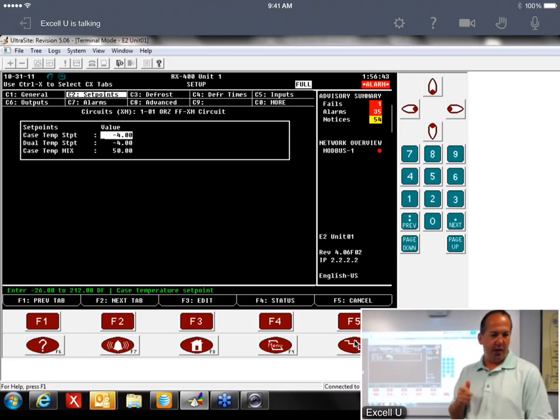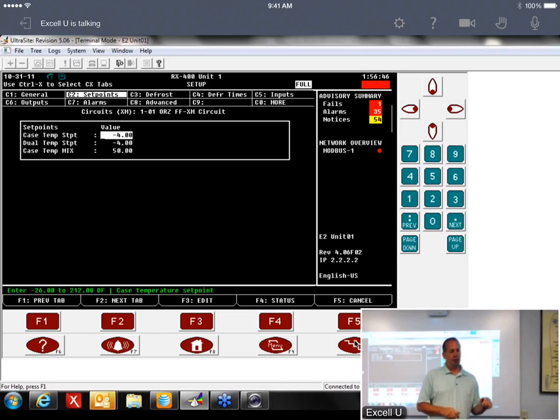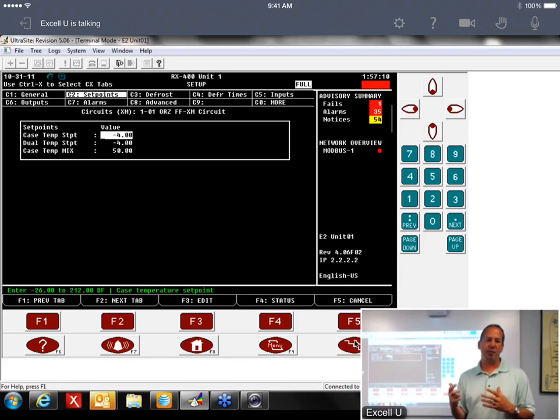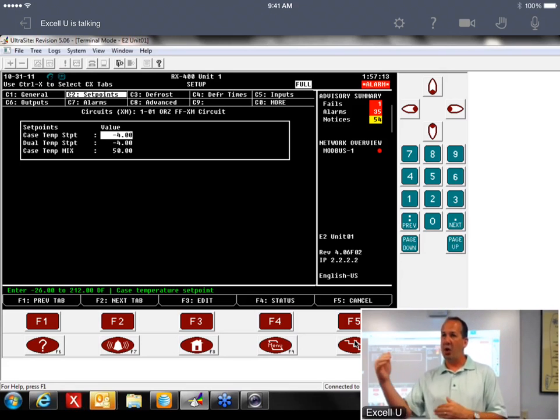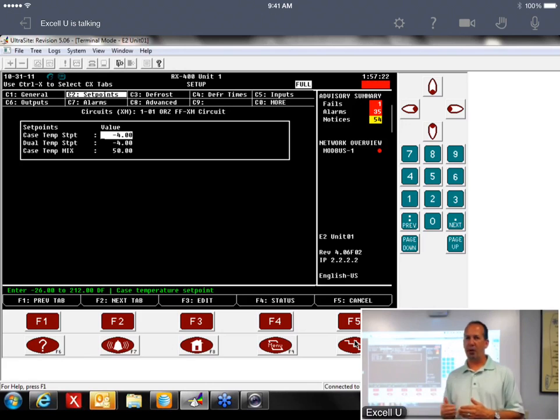And then our Setpoints tab. One thing on the Setpoint that we found, and you may get into some arguments with your coordinator on this, but let's say Hill Phoenix said this set point is -3, and you put -3 in here. What's going to happen is when it gets to -3 degrees, it's going to shut the valve off. So it doesn't really have a set point dead band. When it gets to -3 degrees, it shuts that valve off, and then it may hit -1 before it starts bringing the temp back down. So your average temp is actually going to be -2.